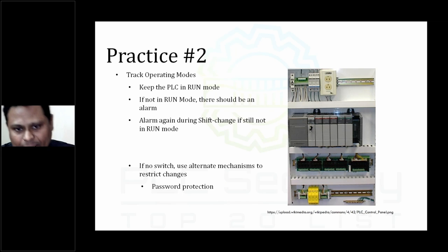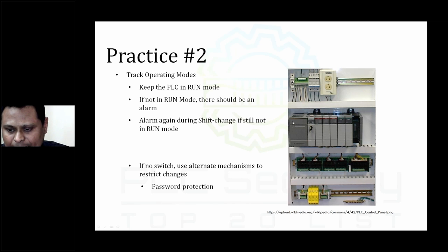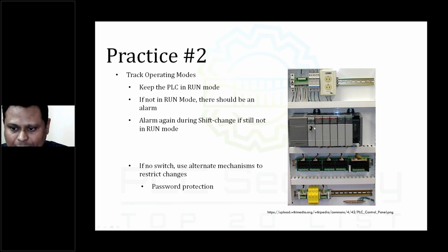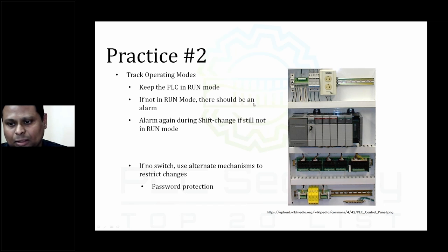Let's start with a simple one — Practice Number 2: Tracking Operating Modes. Those familiar with industrial control systems know a PLC typically has a switch with multiple modes: Run, Program, and Remote. In Run mode the code is executed by the PLC. In Program mode you can download code to the controller. In Remote mode you can choose whether to program or run from a distance via software. The guidance here is to keep the PLC in Run mode, and if it's not in the expected mode, alarm the operator.